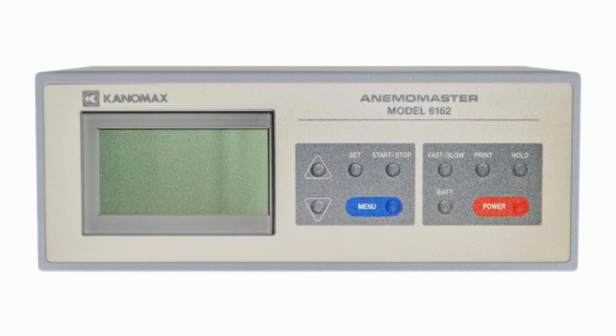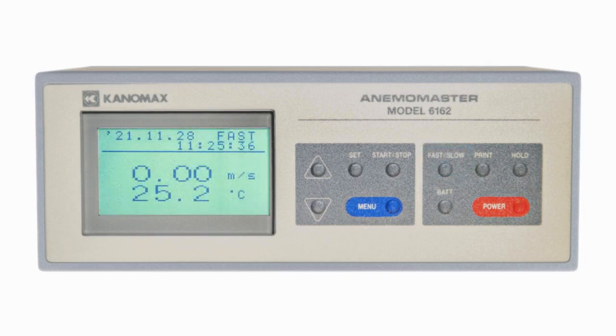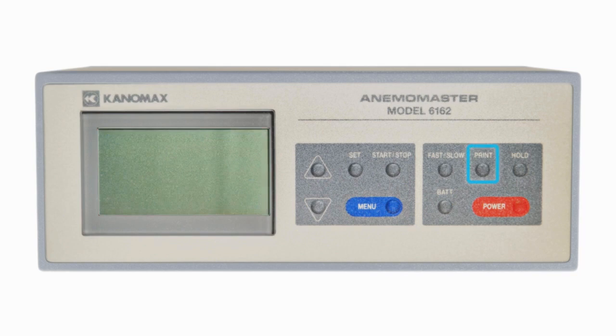The right segment has a Fast/Slow key for cycling through different speeds the anemometer will update values at. Fast mode displays the instantaneous value every 1 second. Slow 1 mode displays moving average deviations for 5 seconds, and Slow 2 mode displays moving average deviations for 10 seconds. The Print key will print a hard copy of a held reading using a connected printer. To hold the screen of a reading, you'll press the hold key.